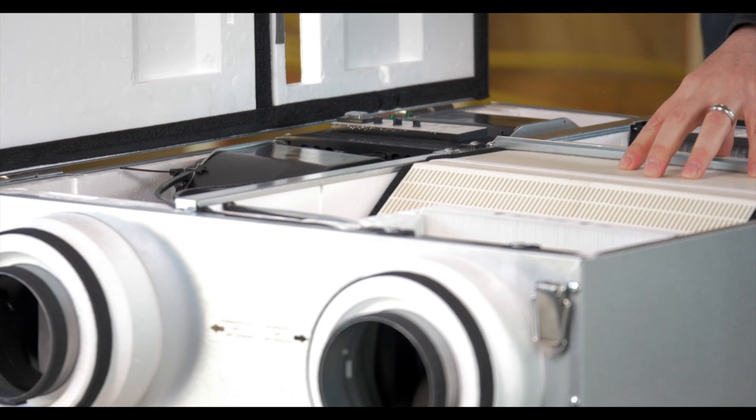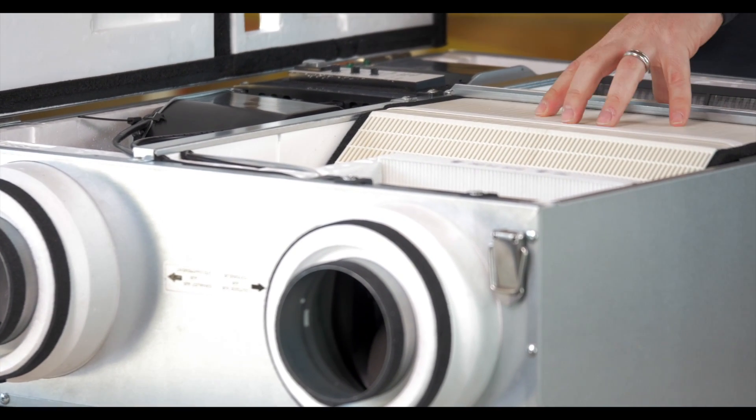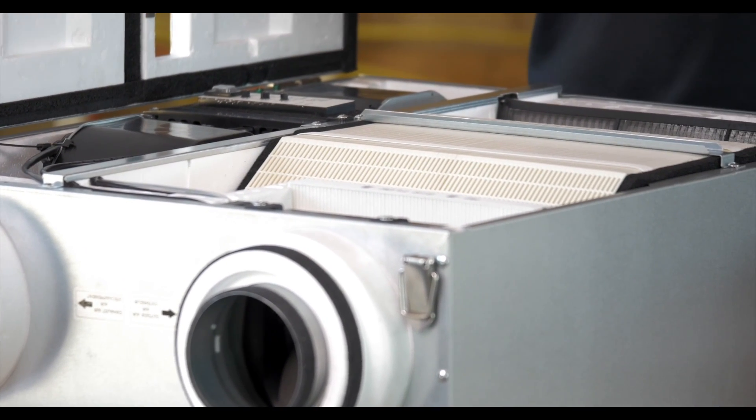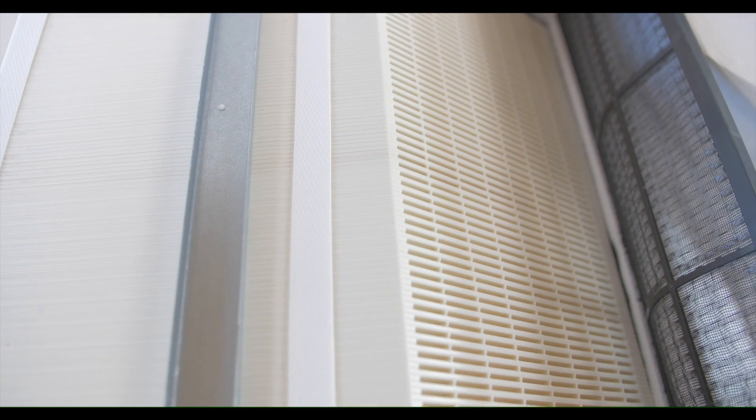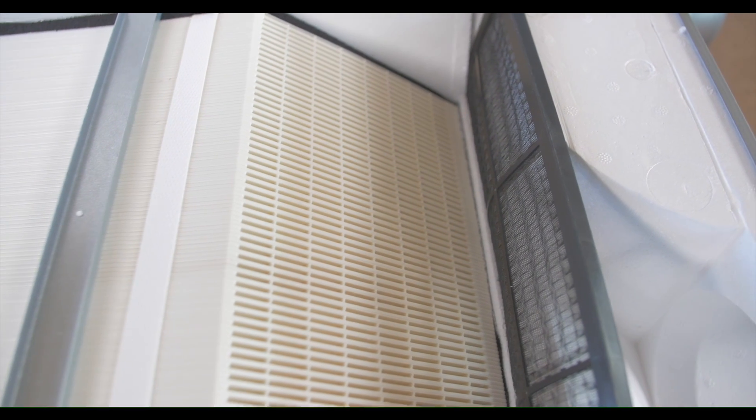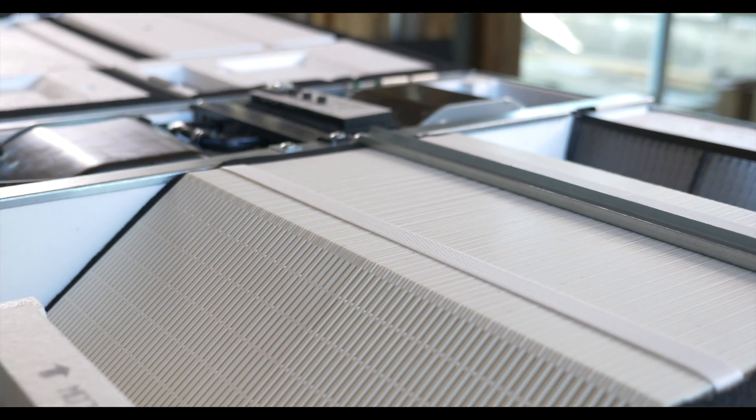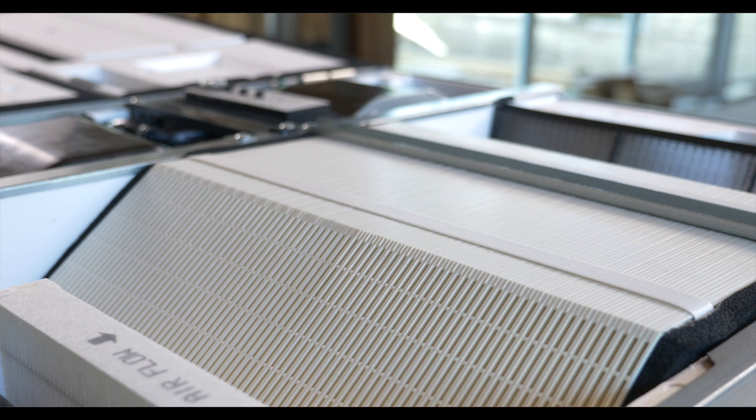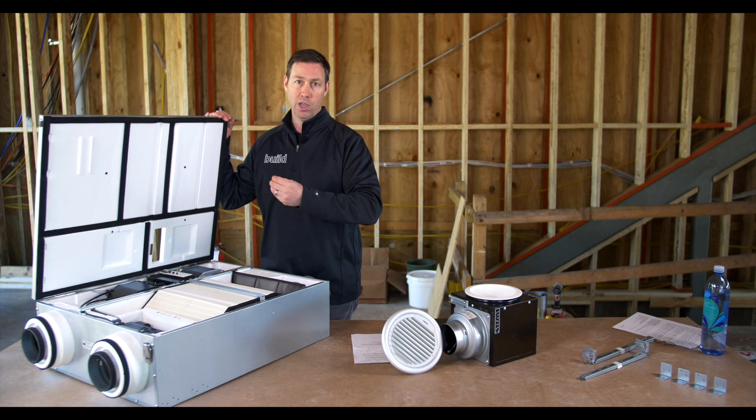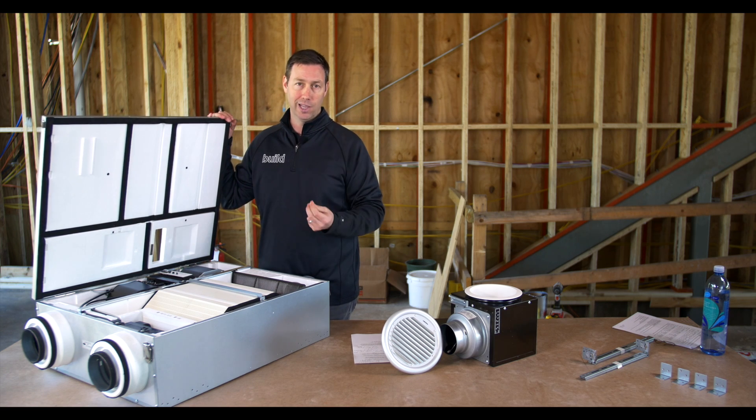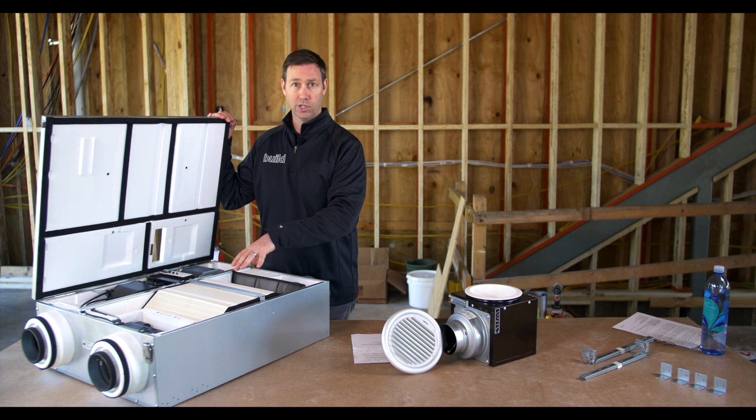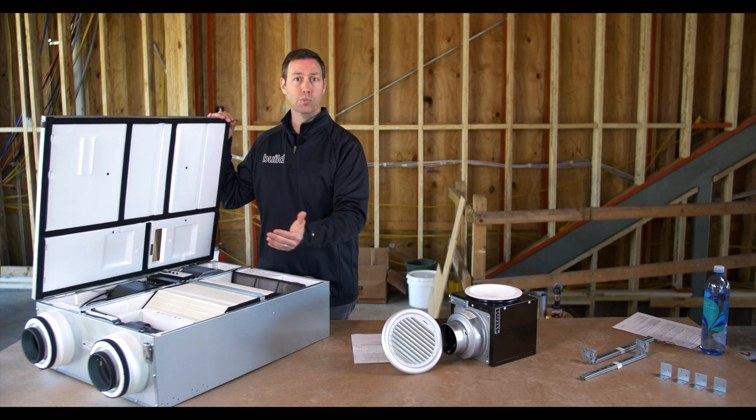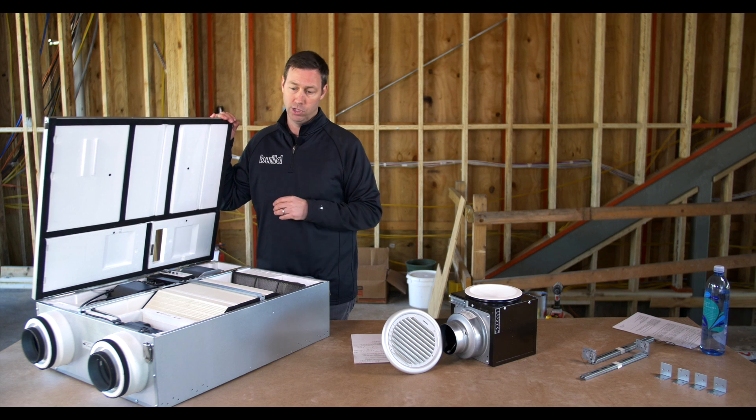Very impressive unit. Of course, here's the heart of the system though. This is the enthalpy core. This is an ERV or energy recovery ventilator. When we bring that fresh air in, especially in our hot, humid climate zones, sometimes we're bringing in very humid air and we want to exchange that humidity from the inside stream to the outside stream so that that air coming in has less humidity in it. The beauty of this ERV is it also functions as HRV duties as well. It's going to move the heat as well as the moisture.